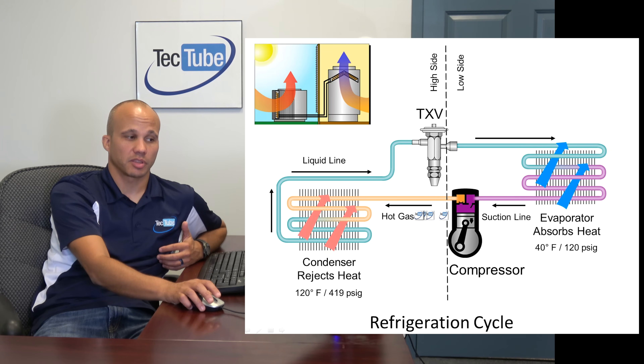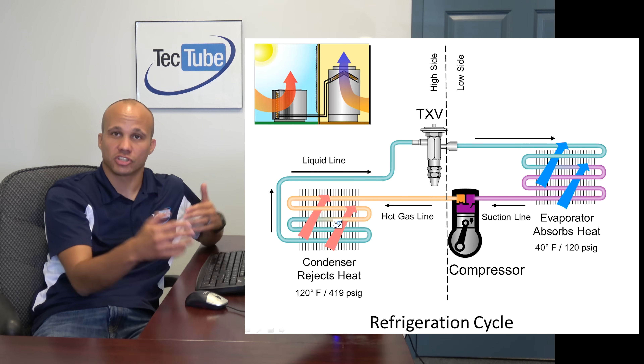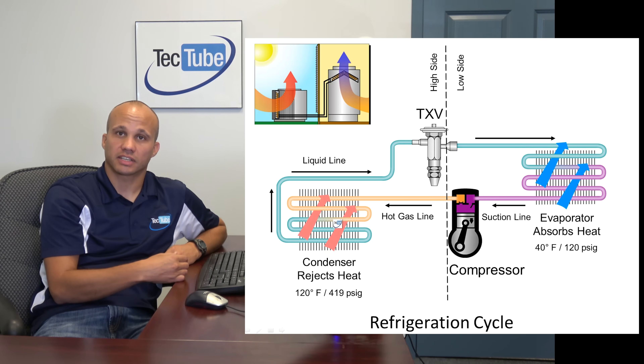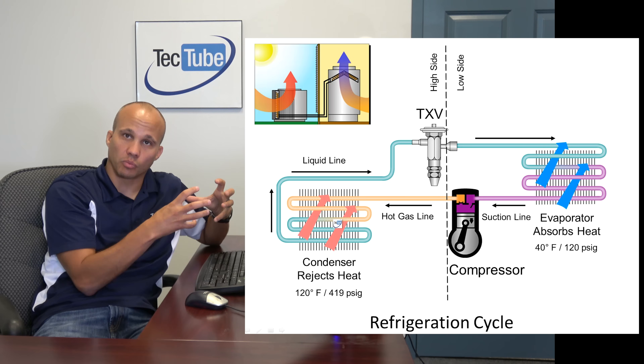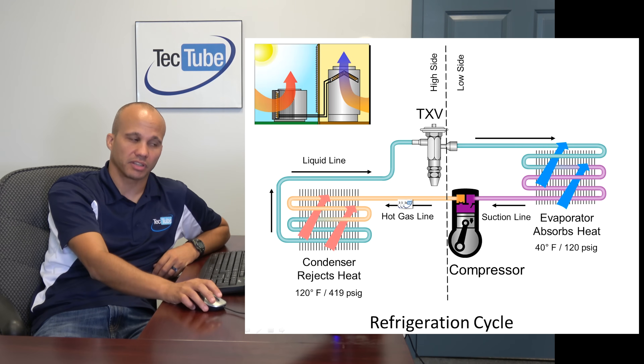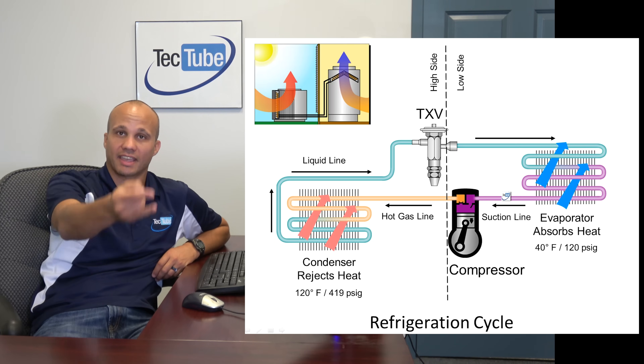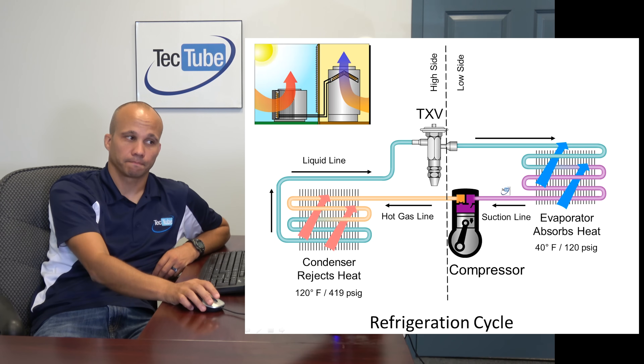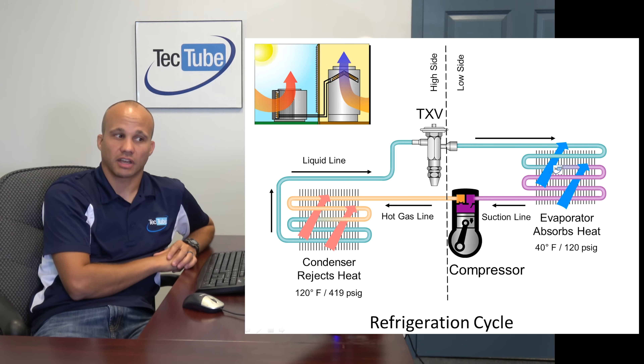Some of the pipes are labeled on the diagram. The hot gas line between the compressor and the condenser is normally internal to the condensing unit, since the condensing unit has both the condenser coil and compressor together — so you don't typically see that hot gas line. The liquid line and suction line are the two lines you see going from outdoors to inside the building. The line between the TXV and the evaporator is typically all within the evaporator coil assembly, so you don't see it unless you remove the cover.